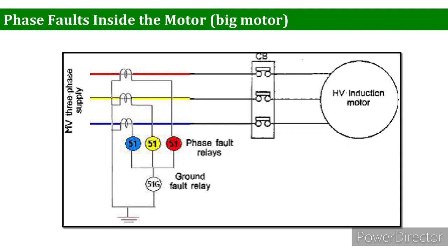There is a circuit diagram. You can see you have an HV induction motor. The CTs are installed on each phase, the R, Y, B, the red, yellow, blue. There is a 51 phase fault relay installed, and also a ground fault relay. It is evident that the high voltage motor is definitely a costly piece of equipment, and the nature of its installation is very critical, because the setup associated with that motor is also very critical, since a large motor is installed at that setup. So this is the basic strategy that we will use to protect the motor against phase faults.